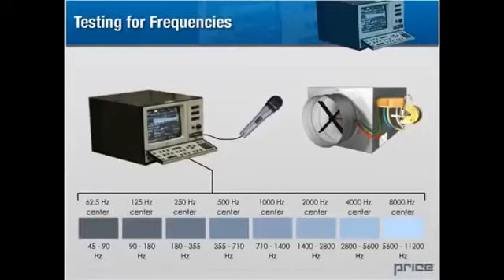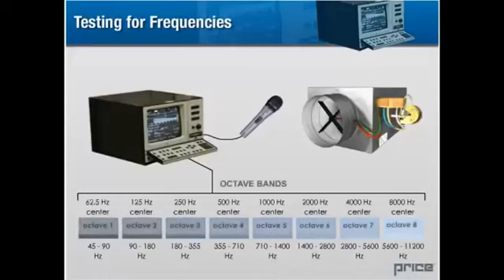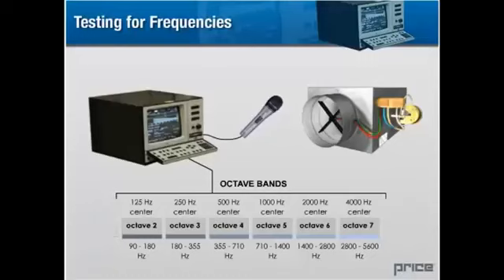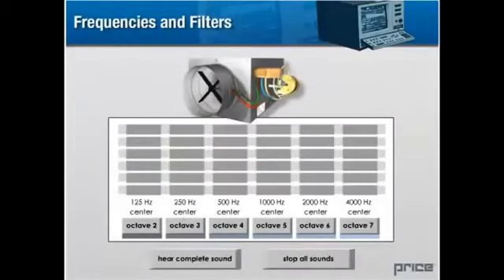A tone with a frequency that is twice that of another is said to be one octave higher. The frequency ranges that we analyze are therefore called octave bands. Because the contributions found in octave 1 and octave 8 are often imperceptible in HVAC applications, we discard the data found in these frequency ranges before publishing results in the catalog. Once the original sound has been separated into frequency bands, we can then measure the loudness of each one independently. Please experiment with this tool to hear the kinds of frequencies that we analyze in our testing facility.